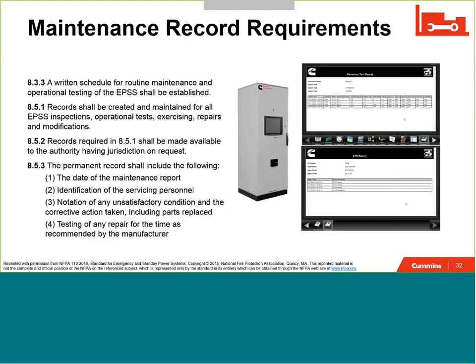One of the last things I'll note here comes back to maintenance records and requirements. This is also clearly called out in NFPA 110. You can see a lot of the details that are required and mandated, down to things like date of maintenance, service personnel, everything that's being done as part of those maintenance records. This is an opportunity to look at your gear or your generator set vendor to find out if there are options available from that vendor to automate some of this for you. More than likely, this testing or maintenance is fairly routine, and any ability to automate this or have this easier to handle, manage, and produce upon request can help to lessen the load on the facility owners and operators.